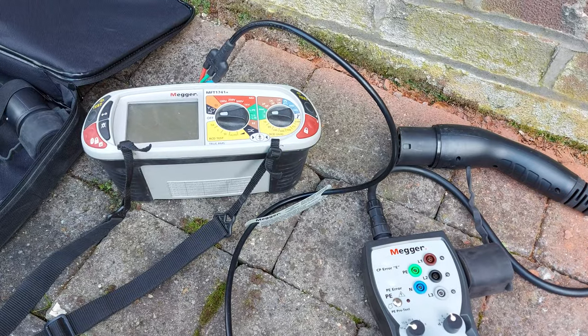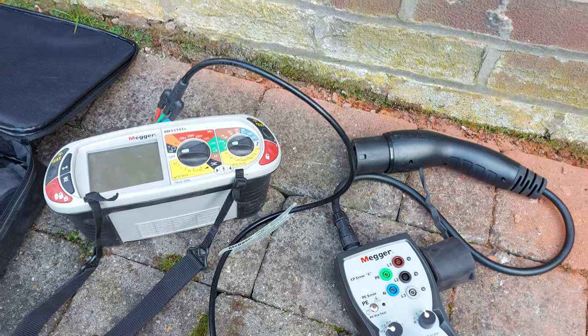Right, well, I've already done the dead tests on this one while I was waiting for the phone to charge again. And I also did it on the last video. So if you want to check out some dead testing, which is R1 plus R2 and insulation resistance, then look at the previous PodPoint video, which should be going up anytime now. So what I am going to show you on this one is using the EV adapter.